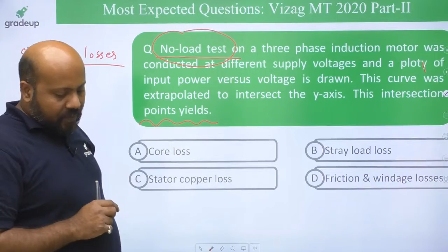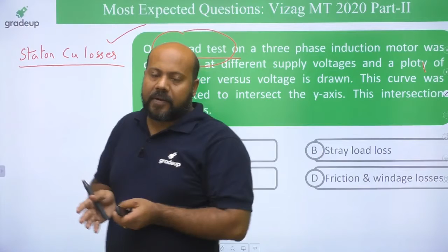When the no load test is performed on the motor, at that point of time, are stator copper losses present or absent? Stator copper losses are present because supply is given to the stator circuit. Motor is on no load, which means load is not connected, but still the motor is rotating. So some current is there in the stator circuit. Current is flowing, so stator copper losses will be there.